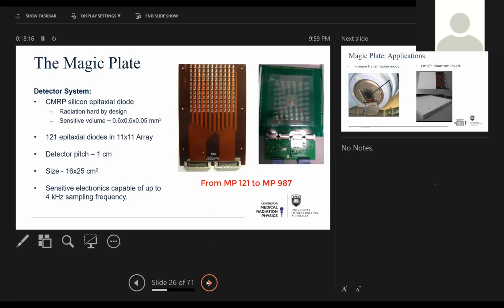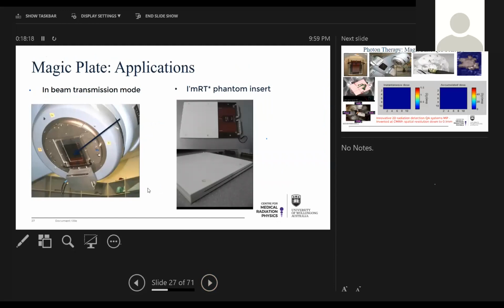What is the advantage of this device? You can use it in transmission mode. When you put it in transmission mode, it absolutely does not perturb the beam, because the thickness is 0.35 millimeter of Kapton, and it does not increase skin dose like other devices such as Delta4 and Dolphin detectors. You're getting an increase in skin dose of 0.1% only, and transmission of 99.8% of the beam. So you can use this system in a phantom and at different depths.